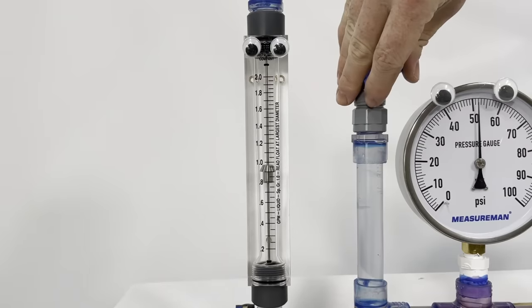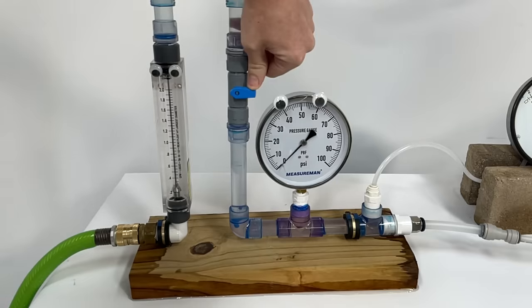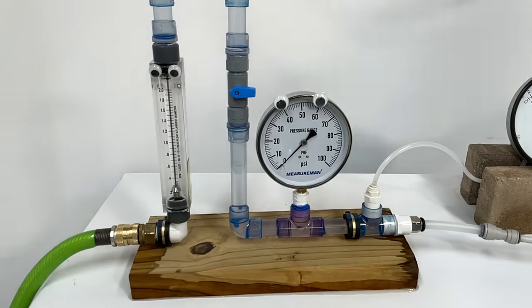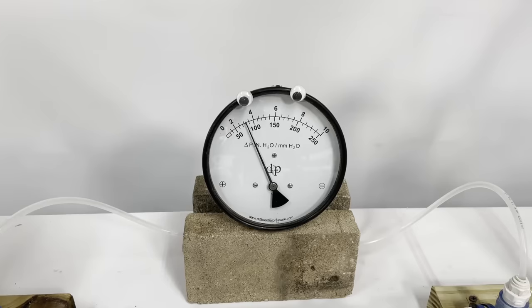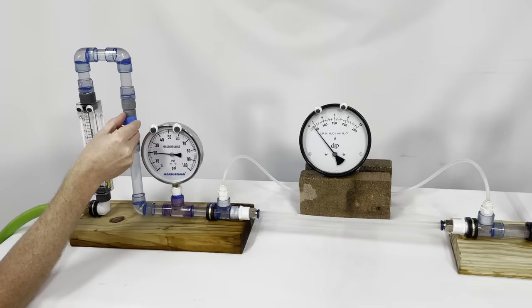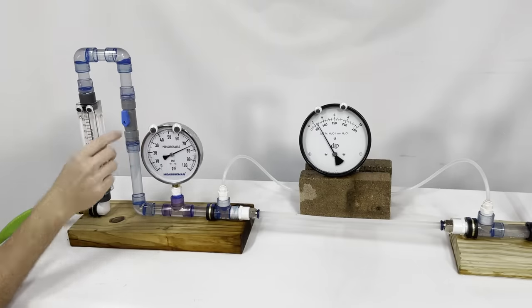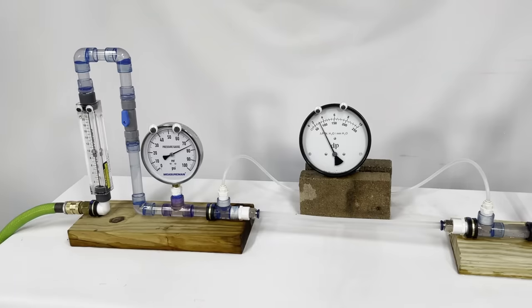The first one measures the flow rate in gallons per minute. The second one measures the pressure in the pipe in pounds per square inch. And the third gauge measures the difference in pressure before and after the sample, also called the head loss, in inches of water. In other words, this gauge measures how much pressure is lost through friction and turbulence in the sample. This is the one to keep your eye on.